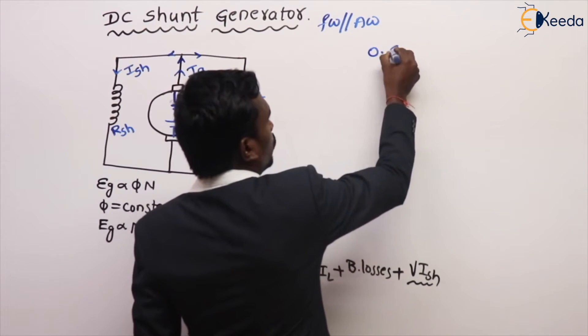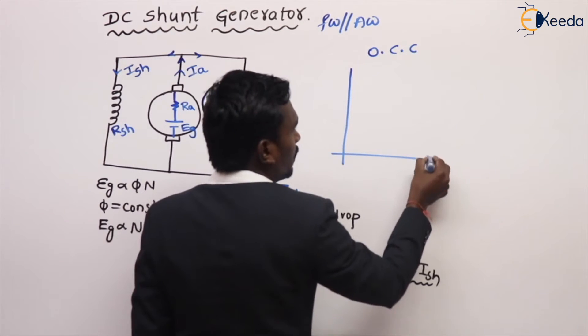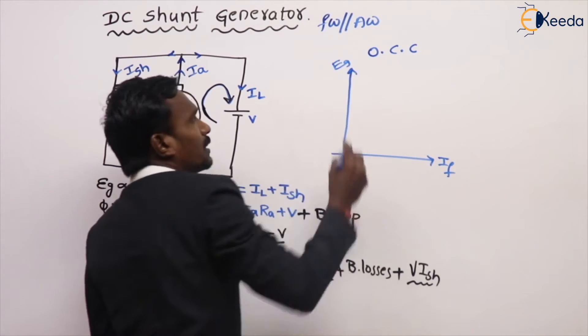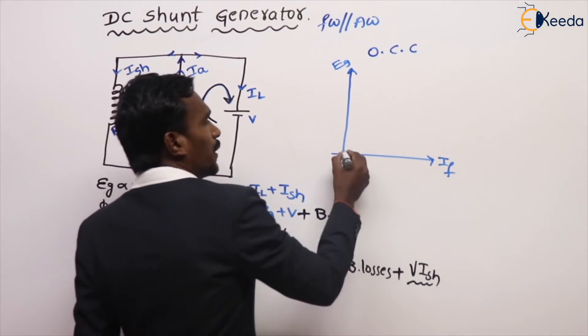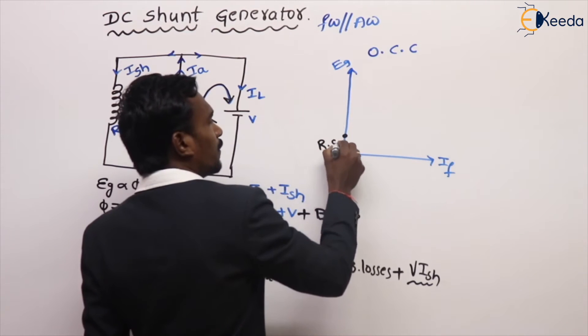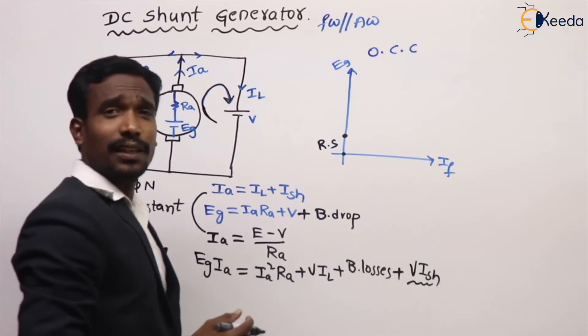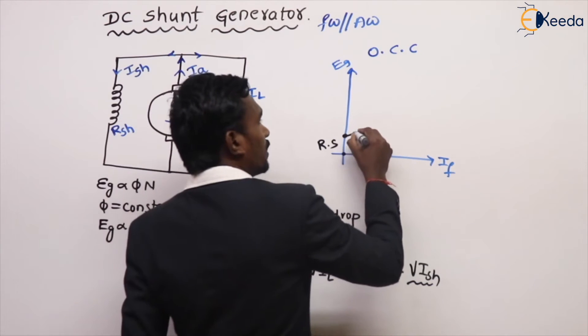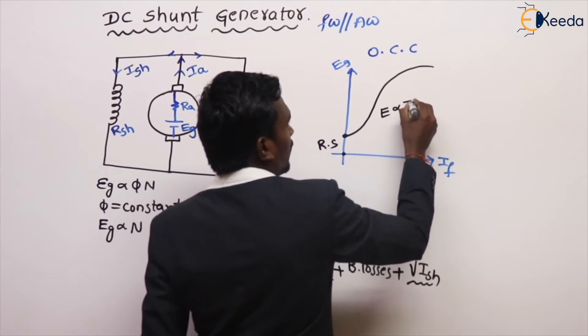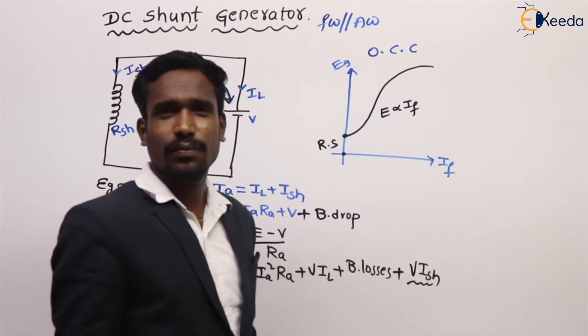Open circuit characteristics are drawn between field current and generated EMF. Even though field current is zero, the generator produces some EMF due to residual flux — residual magnetism — because this is a self-excited generator. When the field current increases, EMF also increases, since EMF is directly proportional to field current, up to saturation.